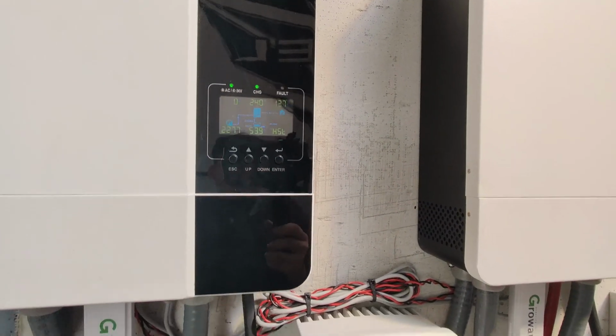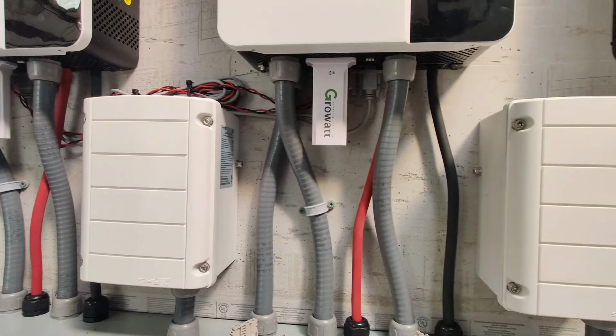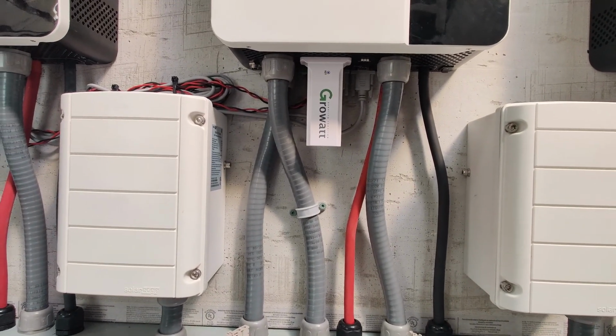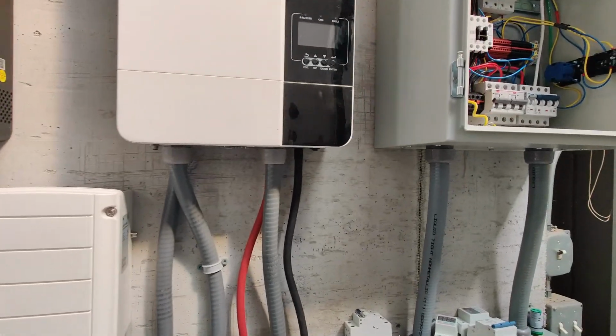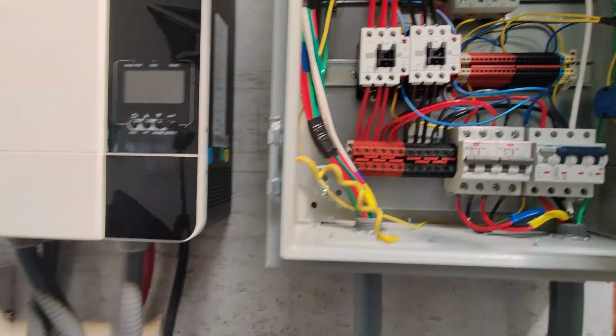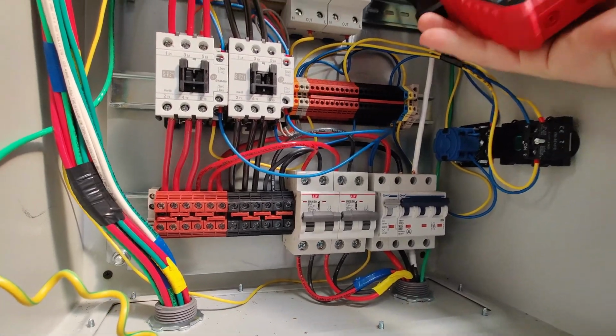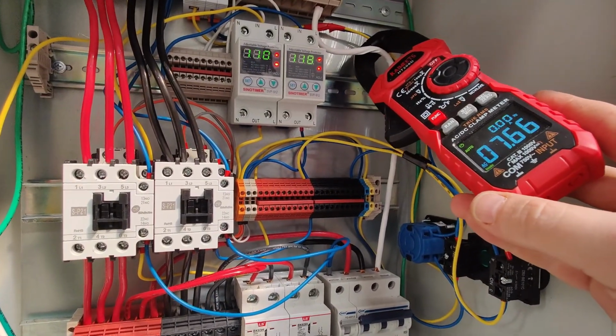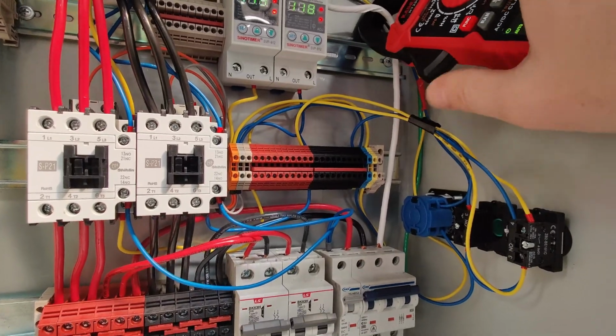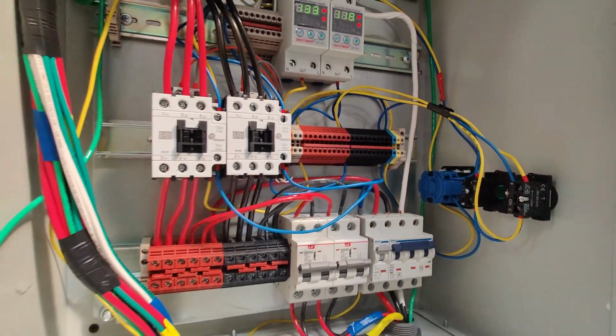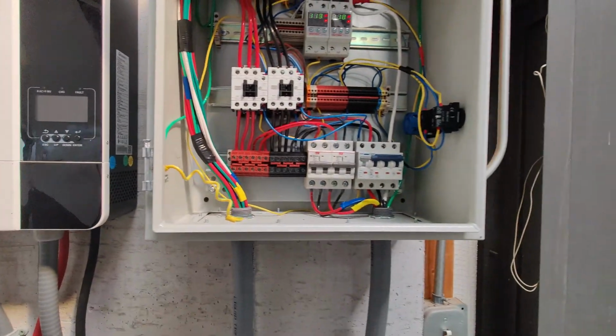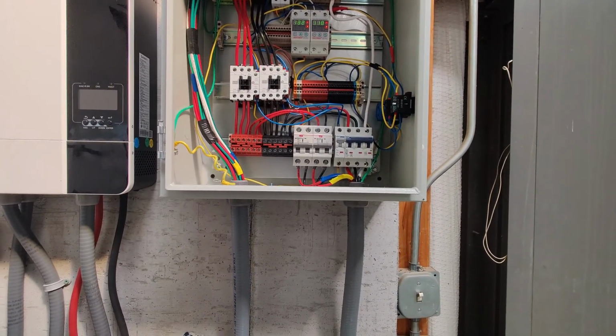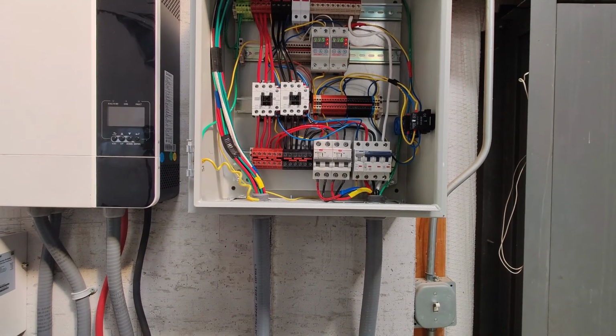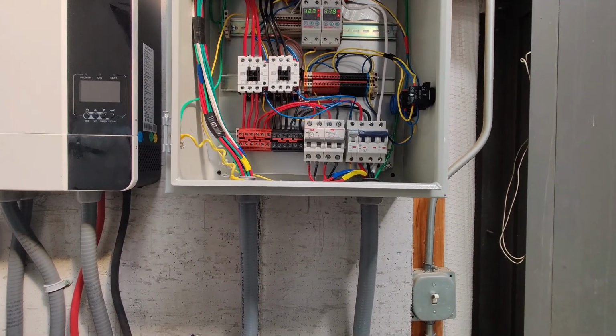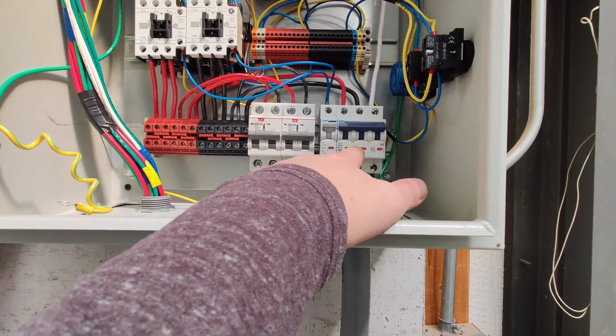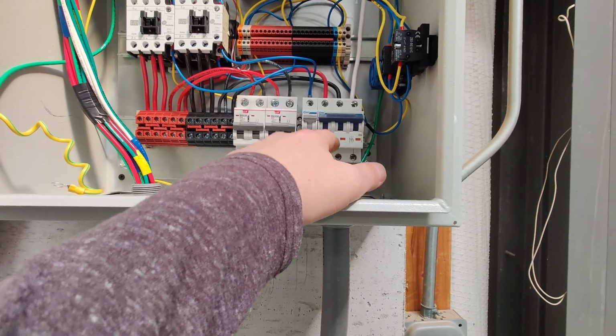17.2, 13.5. If I take my meter and put my meter on here, let's see, I've definitely got electricity flowing through this thing. Go up in here. There we see we've got 7 amps on our neutral leg. Pretty cool, huh? So this all works pretty efficiently. This is about as efficient as I could get things. It should be able to switch up to 63 amps of current. So right now this is only a 50 amp breaker down here, but I do have a 63 amp breaker en route in a 3-pole.